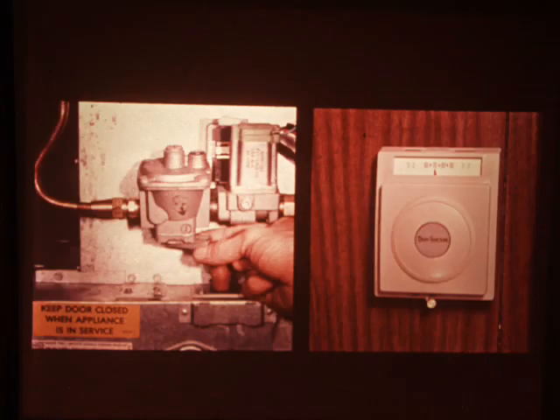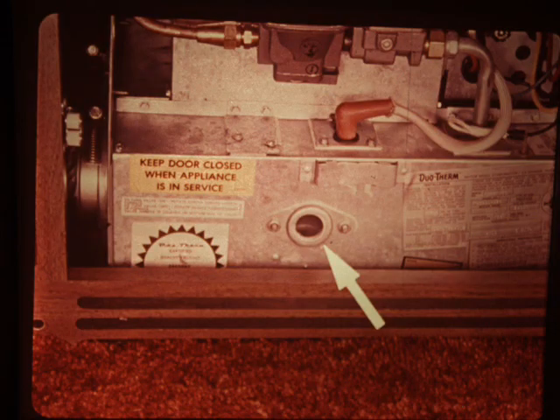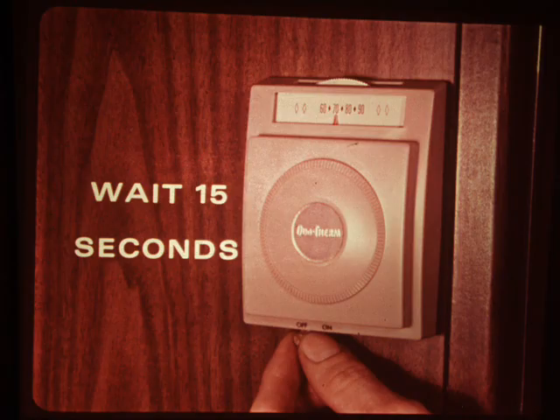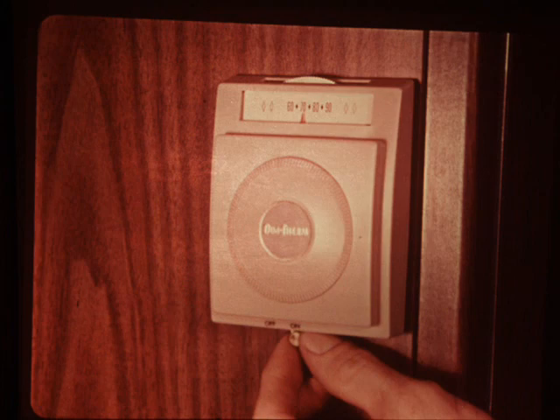Open the furnace gas valve and set the thermostat at a temperature calling for heat and turn the thermostat switch on. Look for a flame in the furnace viewport. If a flame isn't established within 15 seconds, the control module will close the gas solenoid valve. If the burner does not light, turn the thermostat switch off. Wait 15 seconds, then try it again by turning the thermostat switch on again. If the furnace won't ignite after 3 tries, you'll have to do some troubleshooting to determine the cause.